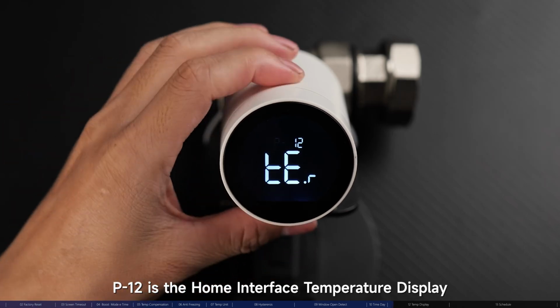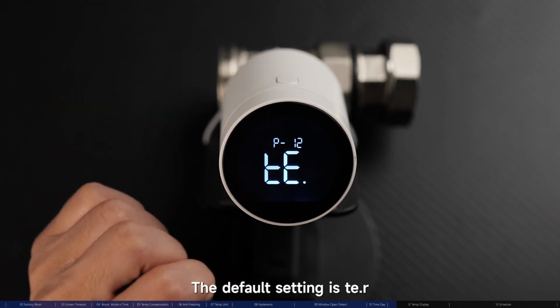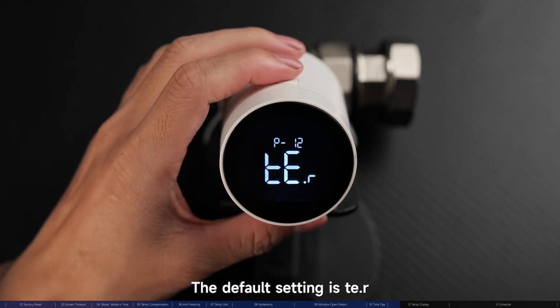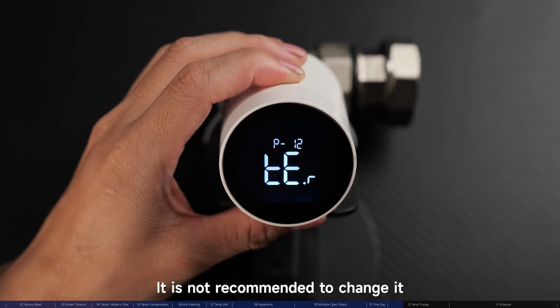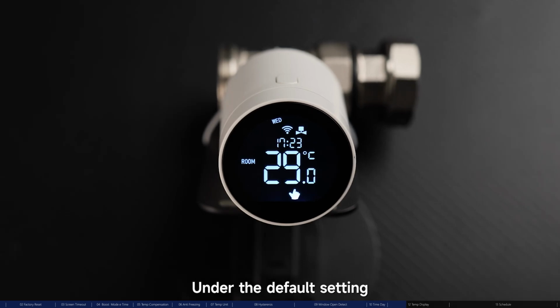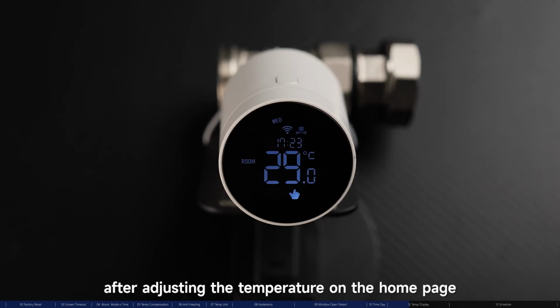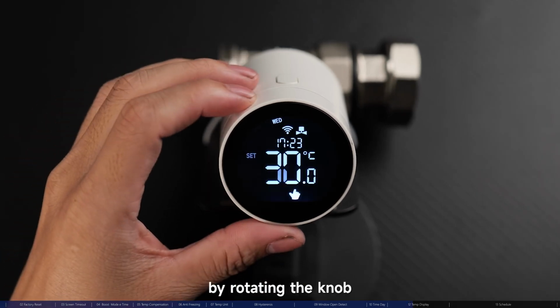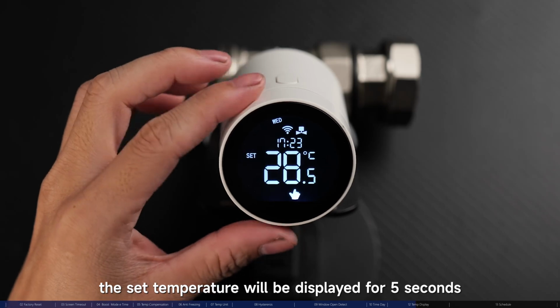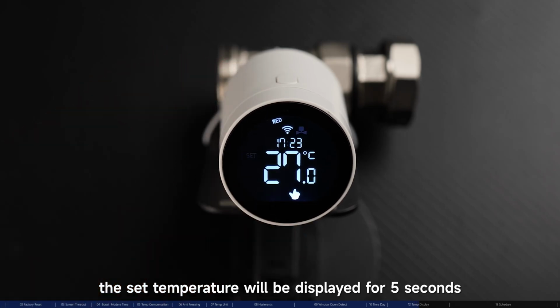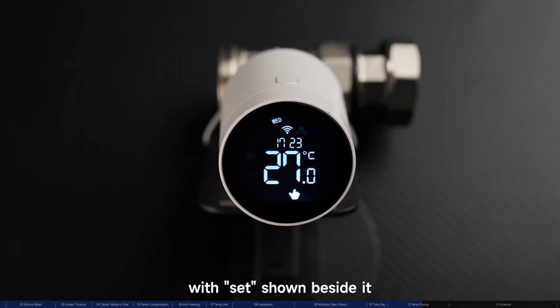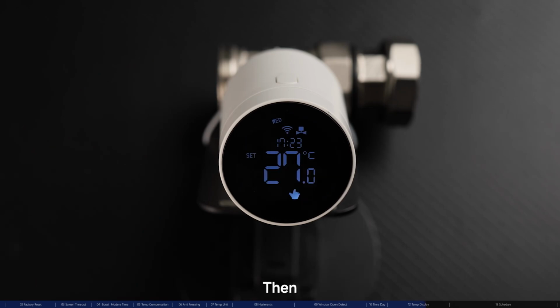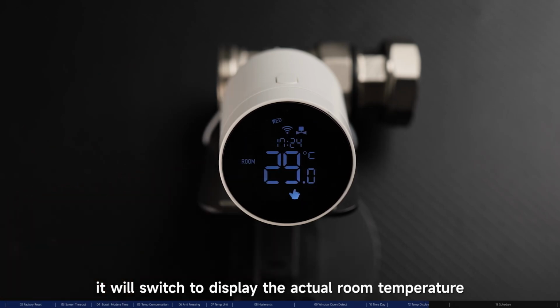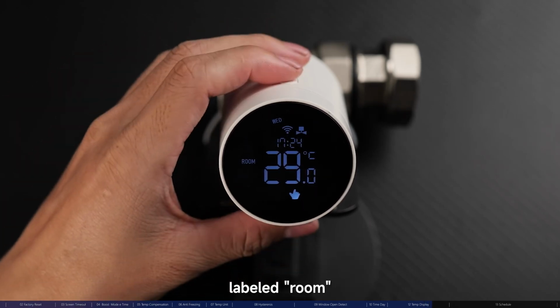P12 is the home interface temperature display. The default setting is te.r. It is not recommended to change it. Under the default setting, after adjusting the temperature on the home page by rotating the knob, the set temperature will be displayed for 5 seconds with set shown beside it. Then, it will switch to display the actual room temperature, labeled room.